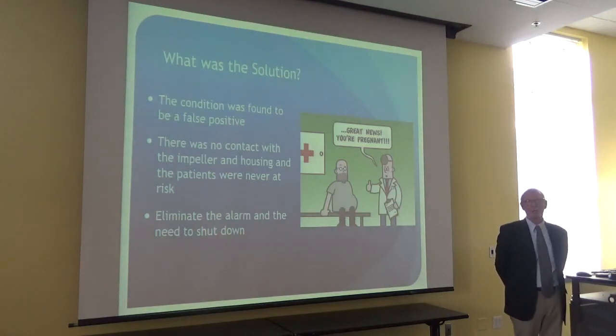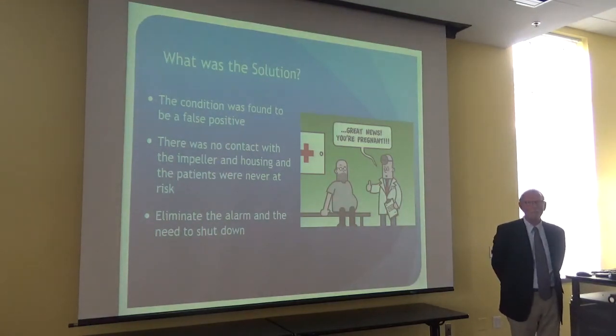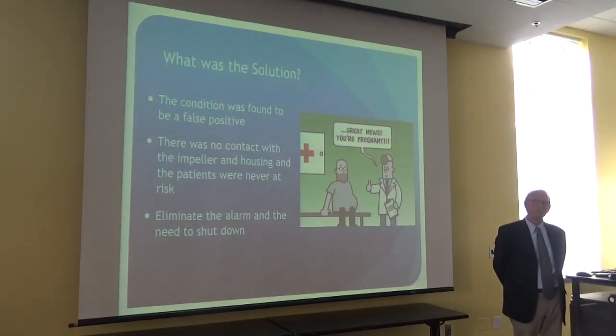And I saw your hand go up. So for the future, would it be wise when designing such medical devices to put a margin of safety over the FDA regulation? The answer is yes, but we assume the standard took that into consideration because it is above and beyond what you would expect. Nevertheless, it's worth testing as wide a range around it as possible.